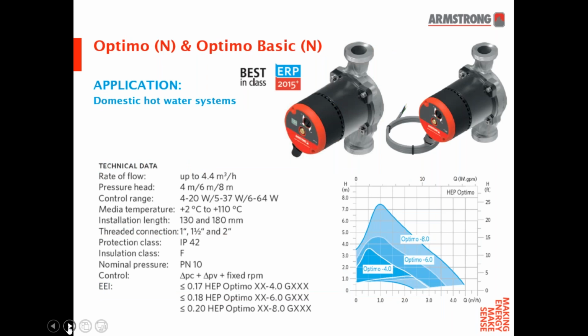So going into the details, the Optimo N and the Optimo Basic N, in essence, other than the body now being stainless steel rather than cast iron, the performance is exactly the same. So rate of flow up to 4.4 cubic meters an hour, pressure head either 4, 6, or 8 meters depending on the specific model, media temperature 2 to 110 degrees centigrade, and the installation length of either 130 millimeters or 180 millimeters. As we said before, this is quite critical for particularly refurbishment projects where the existing pump may well be obsolete, but the face-to-face, the actual installation length, is exactly the same as the majority of pumps in the market in the UK at this moment in time. So threaded connection, depending on the size of the circulator, would be an inch, inch and a half, and 2 inches.